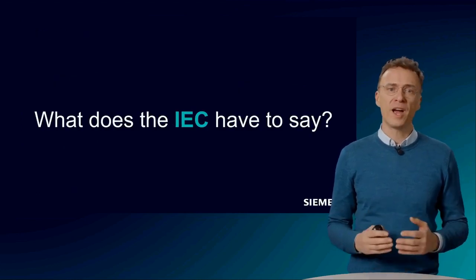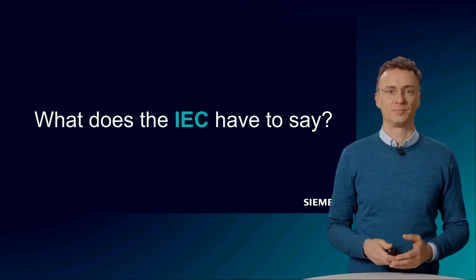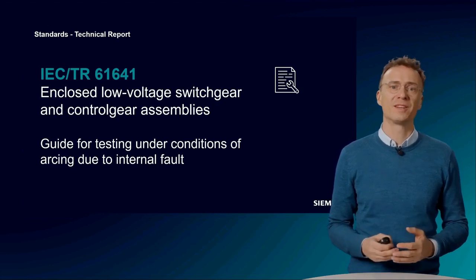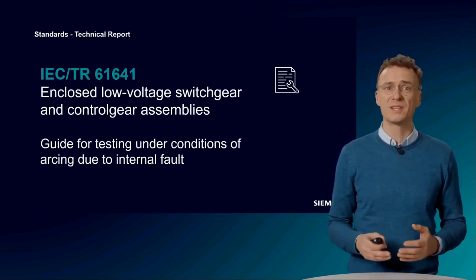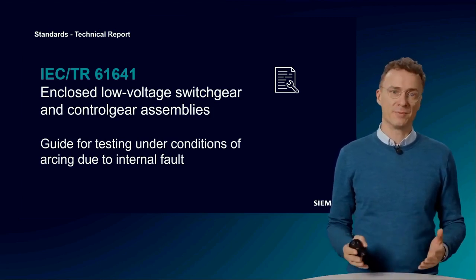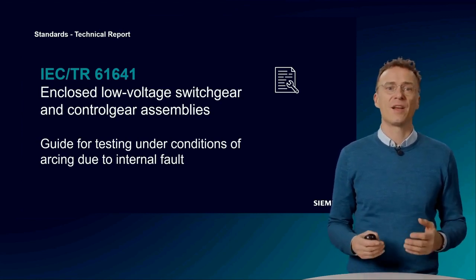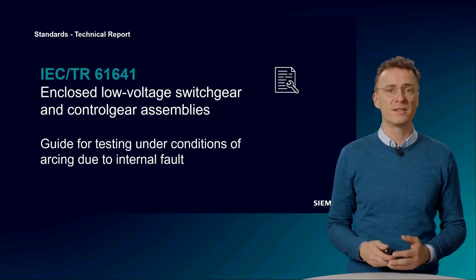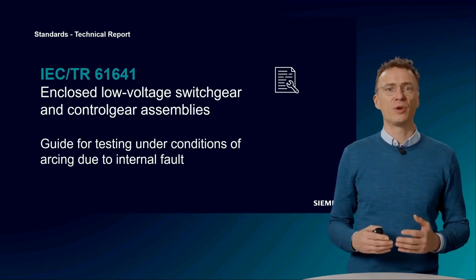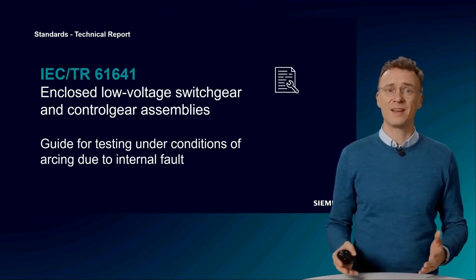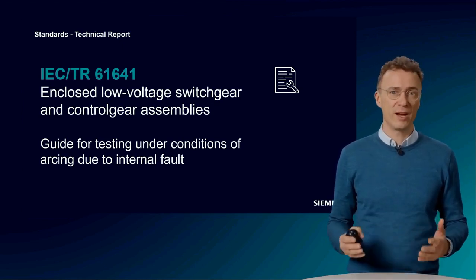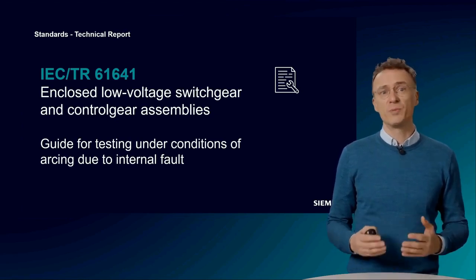A technical report from the IEC standards series is helping us. IEC Technical Report 61641 describes the requirements for testing low-voltage switchboards under the condition of arcing. As a technical report, it is an informative document that reflects the state of standardization but can be incorporated into standardization work later. No measures are defined on how to achieve arc fault protection — this is left to the manufacturer. However, it defines how the test is to be carried out and how the test result is to be evaluated.